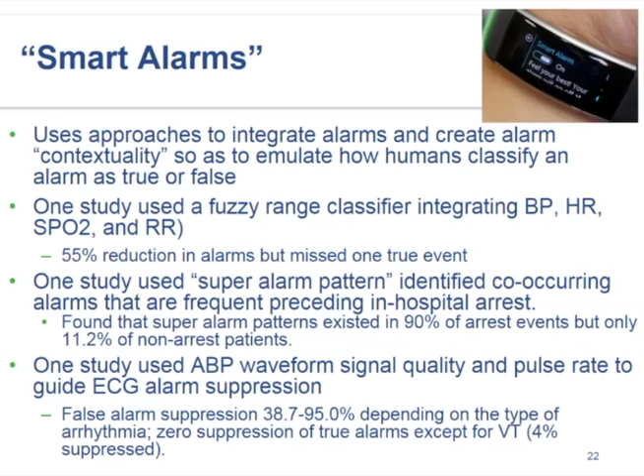And again, the example I gave before was tested in one study where they used the arterial blood pressure waveform and pulse rate to guide an ECG alarm suppression algorithm, and found that false alarm suppression ranged anywhere between about 40% to almost 95%, depending on the specific arrhythmia they looked at. They also wound up with zero suppression of true alarms, except for ventricular tachycardia. And as we mentioned on the previous slide, ventricular tachycardia false alarms seem to be a particularly difficult area to make headway on.